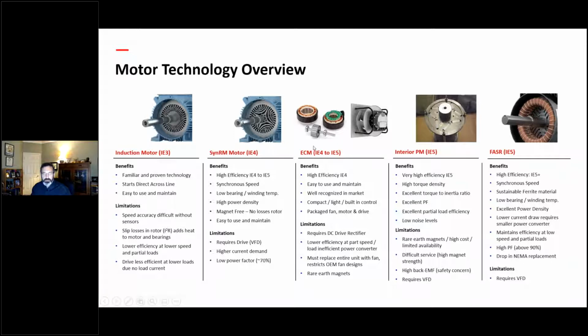All of these other technologies that you see going to the right are to address going to higher efficiency technology. Synchronous reluctance motors, or SynRM motors, are basically one of the first technologies that came out. And the whole idea in a motor is the only way you're going to get to higher efficiencies is you have to eliminate losses in the motor. And there are two fundamental places you get losses in the motor. It's either in the stator windings due to resistance and losses putting current through the wire, or it's circulating I²R losses in the rotor. So what a synchronous reluctance rotor does is it puts air gaps into the rotor that channel the magnetic lines of flux and they basically produce a no loss rotor. And when you reduce the losses in the rotor, it eliminates about 20% of the losses overall, which boosts you from an IE3 motor to IE4.